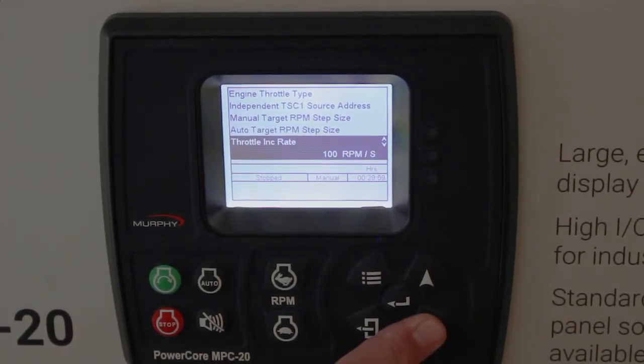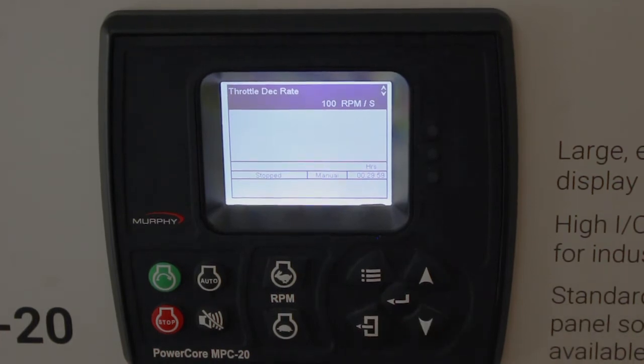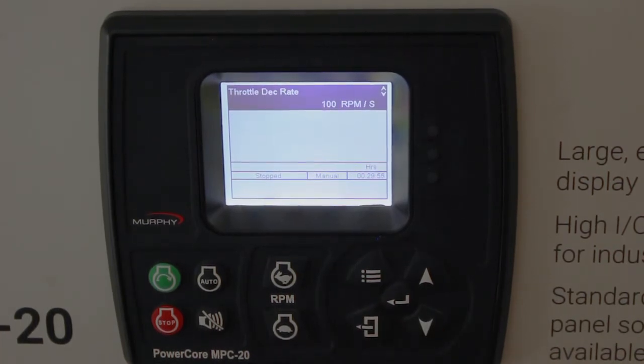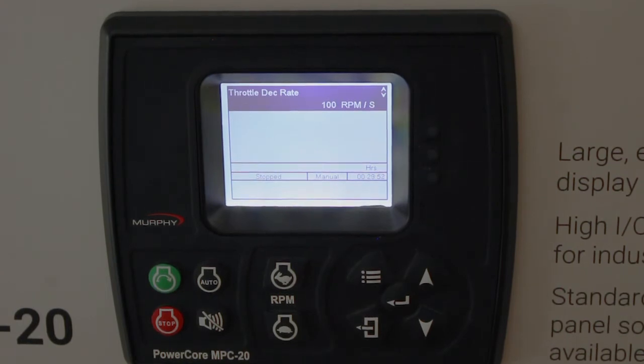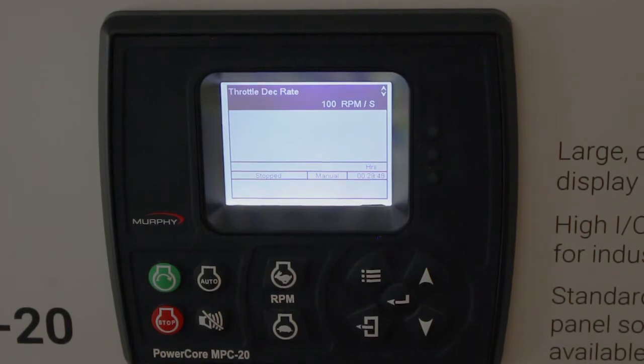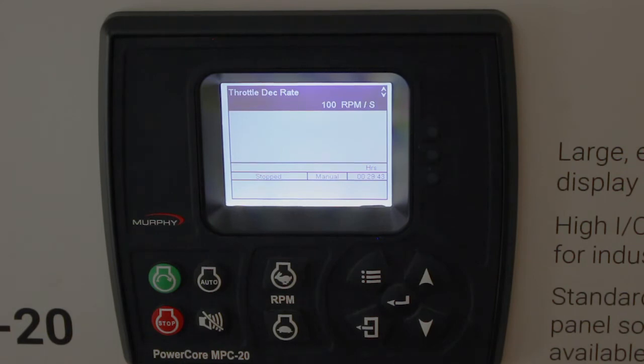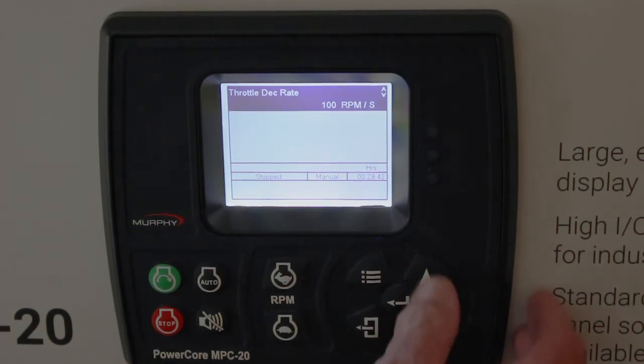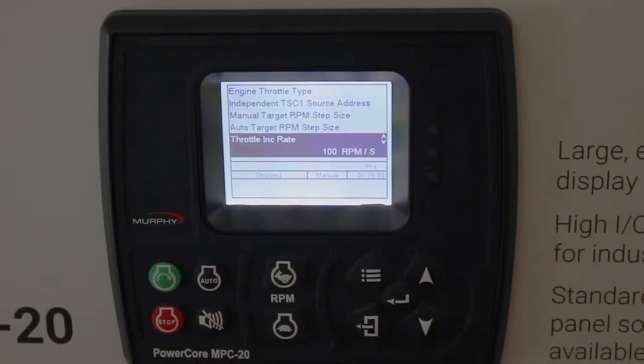Throttle rate increase and throttle rate decrease defaults to 100 RPMs per second. That's how fast we're going to try to track that target RPM. You can adjust that up or down if you get some hunting in auto, or if it's not reacting fast enough and it's lagging too far behind the target RPM. You can adjust these two to take care of that.